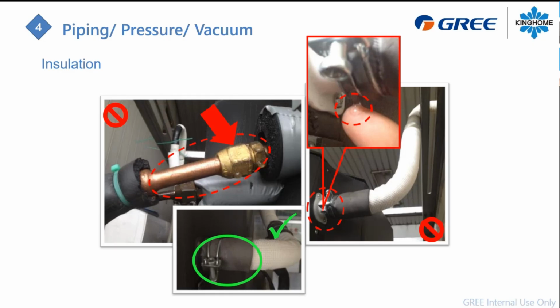The liquid line. Make sure when you add your Armaflex onto the pipe, you make a good contact, so the air or the water cannot condense on the suction line. Make sure you have enough Armaflex and it's tight, so it won't produce any condensate water on the piping.